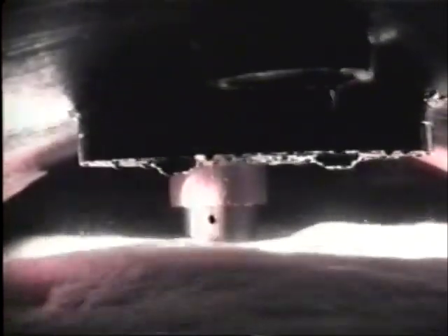Boiler B was allowed to operate with the TDS control disabled until a TDS of 5,600 ppm was reached. The normal operating TDS for this boiler is 3,000 ppm. We can see immediately that the appearance of the boiler water has changed. The bubbles on the water surface have a foamy, creamy appearance and are much smaller and slower to burst than at normal TDS levels. The surface of the water appears calmer.